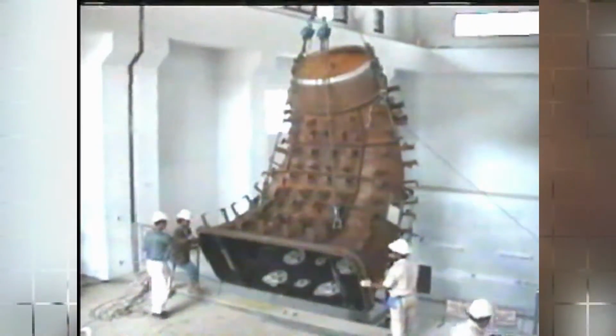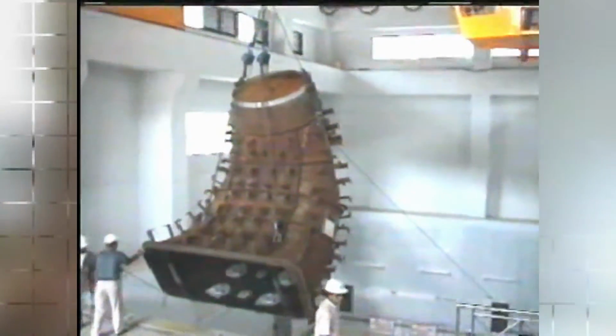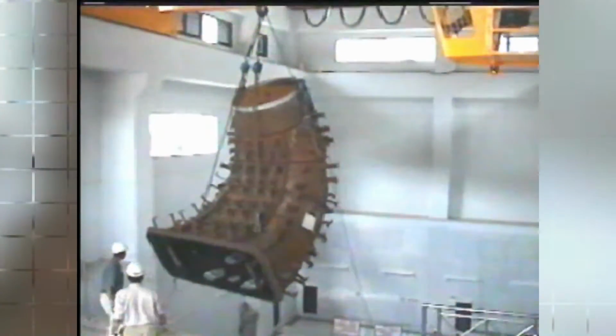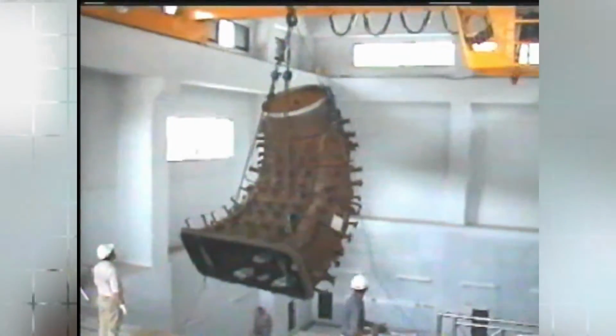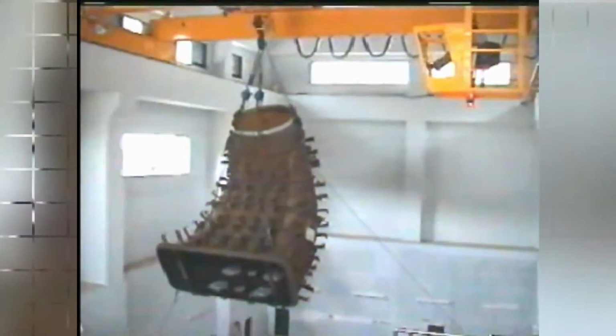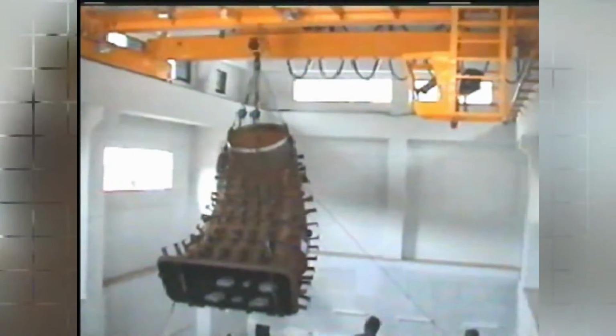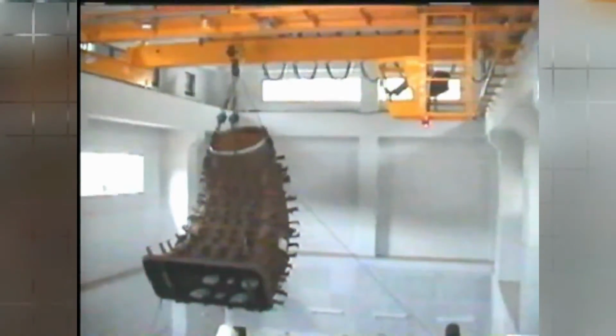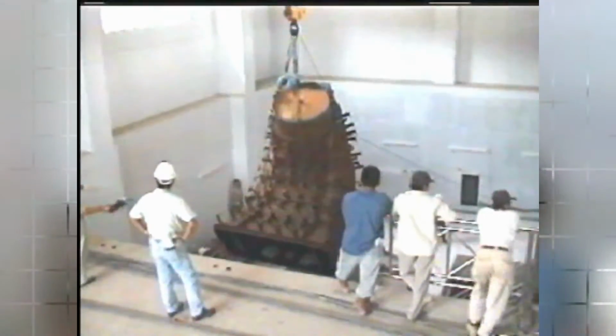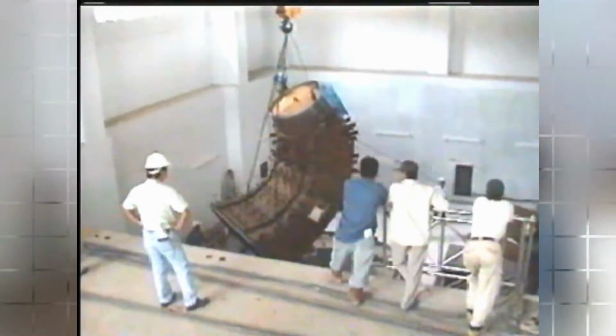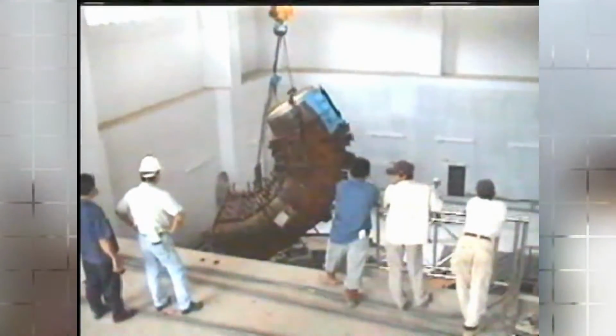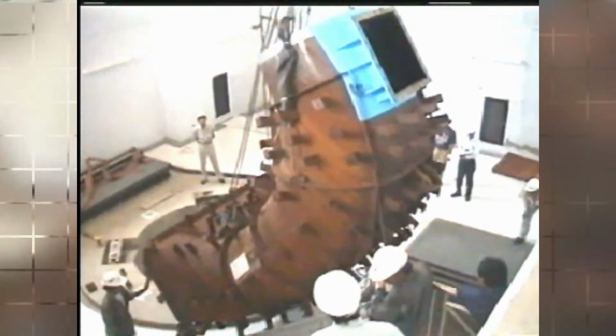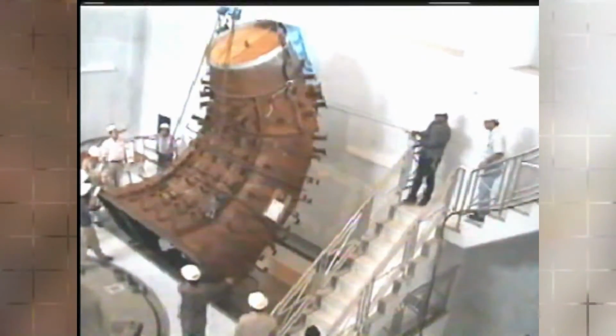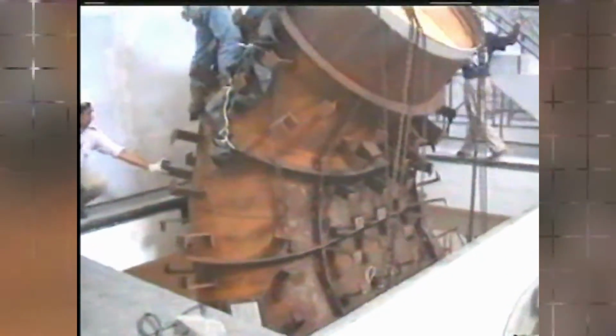The draft tube of the elbow type can be made of steel liner not less than 12 millimeters thick, and can be supplied to a point 3,000 millimeters downstream from the vertical center line of the turbine. Beyond this portion, the draft tube will be formed with concrete to the shape as designed, but clear opening at the draft tube outlet shall be 3,200 millimeters in width and 1,900 millimeters in height. A sufficient number of leveling screws or jacks and anchor rods with turnbuckles is provided for centering, leveling, and securely holding the liner in correct position during assembly, and concrete will be placed by the civil contractor according to the contractor's instructions.